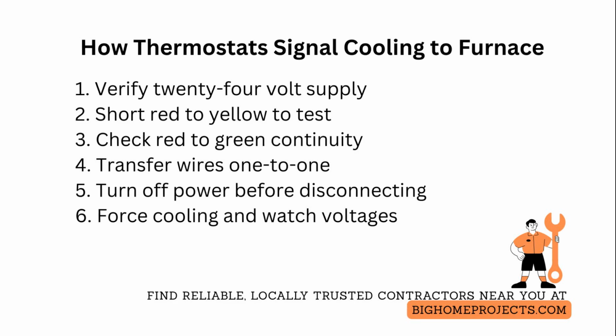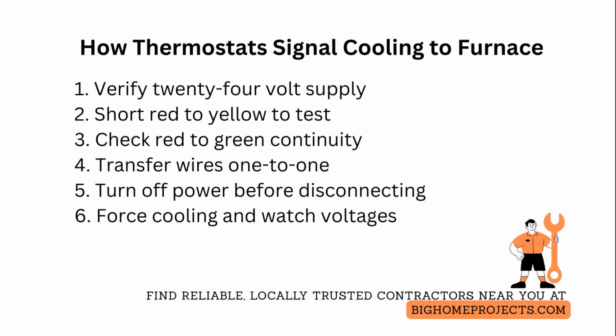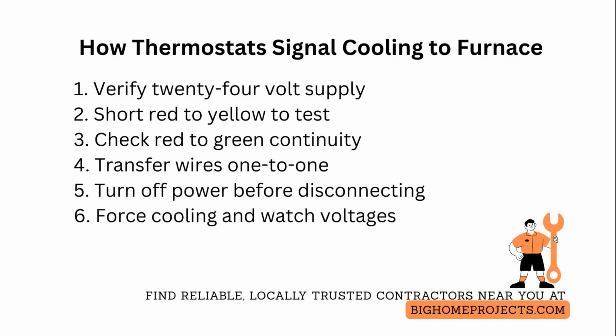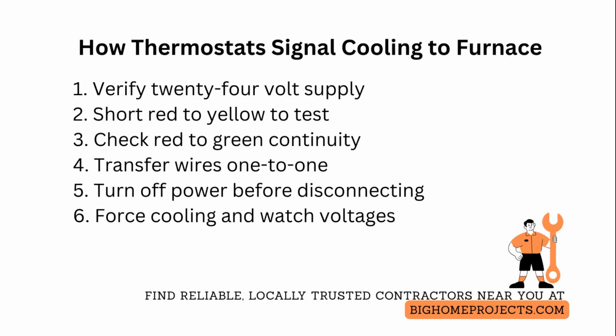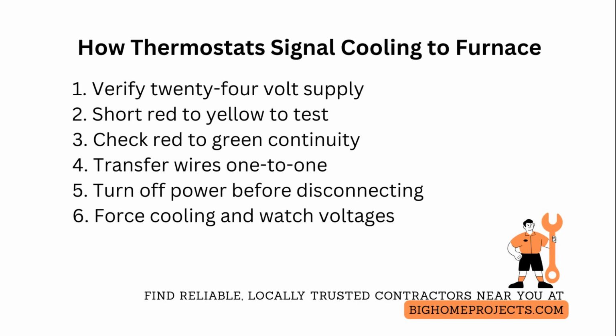Start by verifying you have 24 volts between the red and common at the thermostat and again at the air handler control board to rule out transformer failure. If voltage is present at red but missing at yellow on call, test continuity through the thermostat or use a meter to short red to yellow at the thermostat terminals to simulate a call for cooling. If shorting red to yellow energizes the outside unit but the fan does not run, check red to green continuity and then measure 24 volts at the blower relay coil on the control board when the thermostat is calling. A missing 24 volt signal at the control board indicates either a broken wire, poor terminal connection, or failed thermostat.